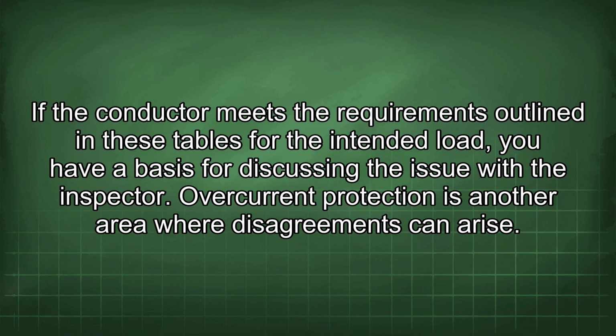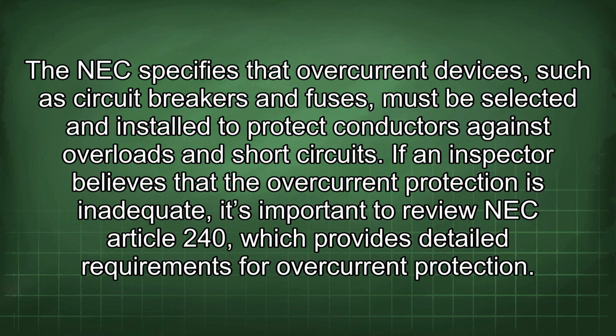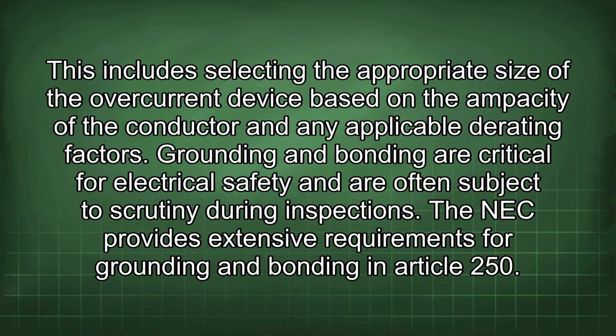Overcurrent protection is another area where disagreements can arise. The NEC specifies that overcurrent devices, such as circuit breakers and fuses, must be selected and installed to protect conductors against overloads and short circuits. If an inspector believes that the overcurrent protection is inadequate, it's important to review NEC Article 240, which provides detailed requirements for overcurrent protection. This includes selecting the appropriate size of the overcurrent device based on the ampacity of the conductor and any applicable derating factors.